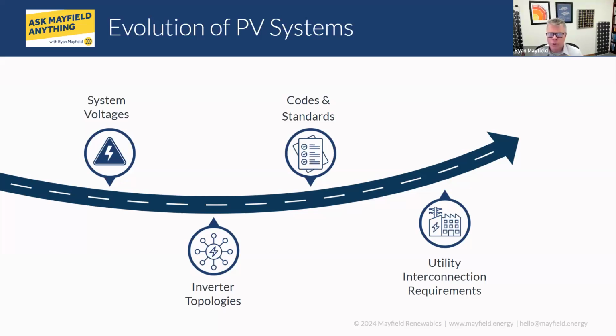Yeah, and I think it's probably worth noting, everything's still going to be bonded together. We're not losing that. So, making sure that we are using our language right, our systems are still going to have a reference to ground, especially ground mount systems. You put all that metal into contact with the earth, and electrically the modules are bonded together, and so the systems are connected to the earth. They are grounded. We're going to maintain that EGC, the equipment grounding conductor, or the bonding, running to the inverters themselves. So we're eliminating these transformers, which is what was requiring those dedicated DC grounding systems, really, is what it comes down to. And so I have yet to see a system where you can do it.